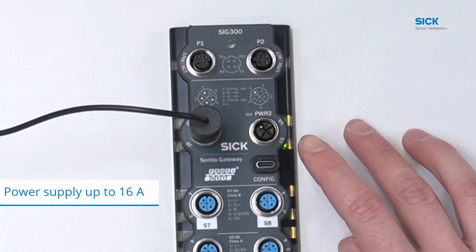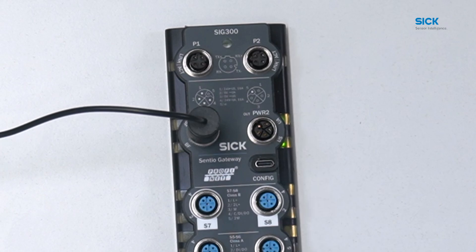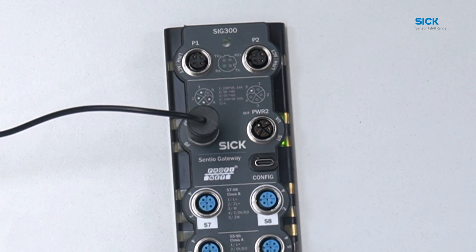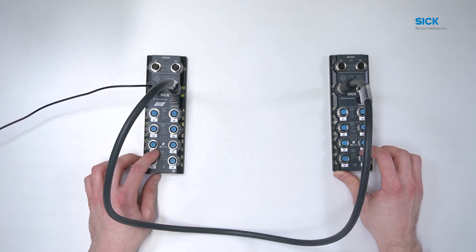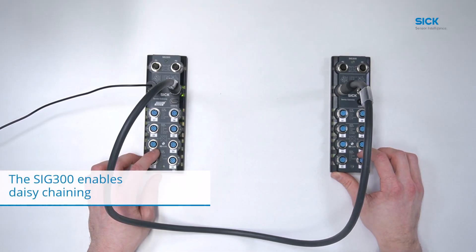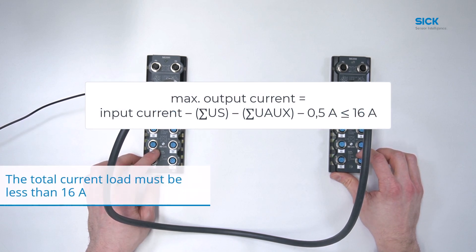Next to the input power port is an L-coded female power out port. With the power out option, other devices can be connected in series to the SIG300 to simplify wiring. Now we have connected two devices in chain. It is important to note that the total current load of your SIG300 and any devices connected in series must be less than 16A.